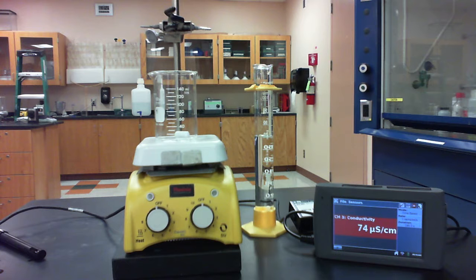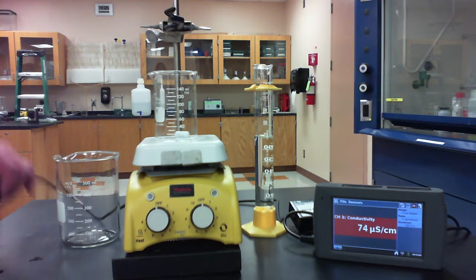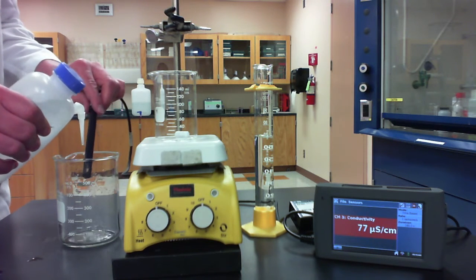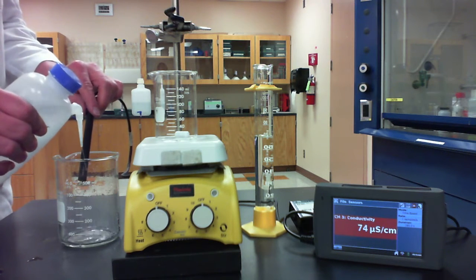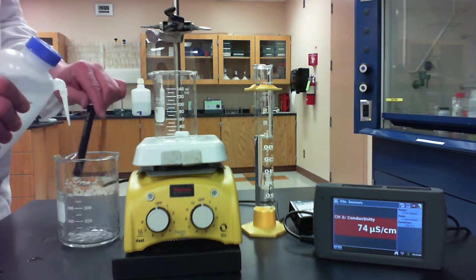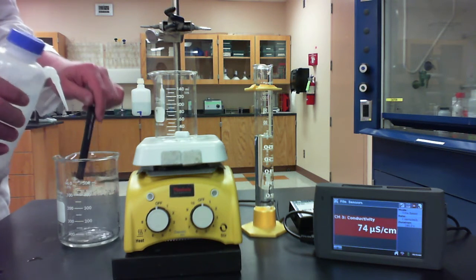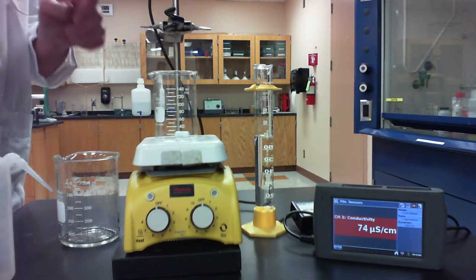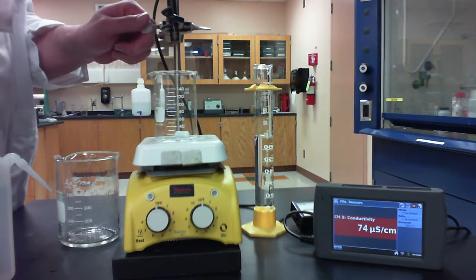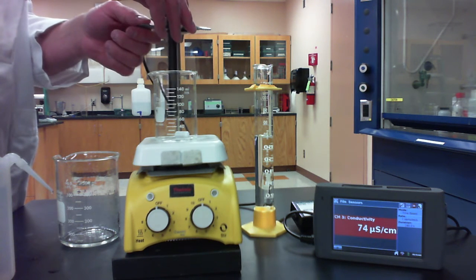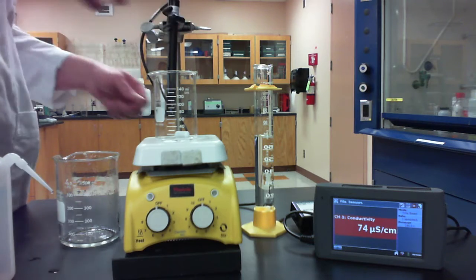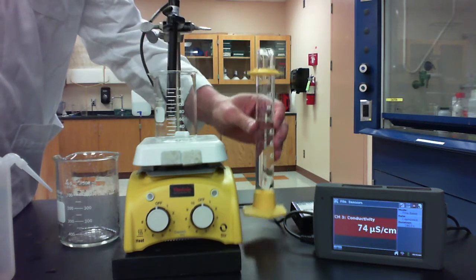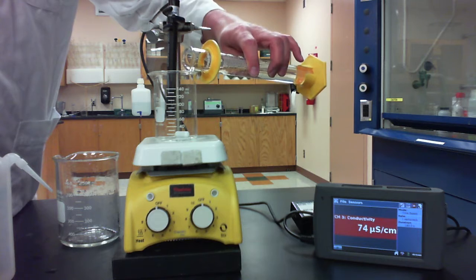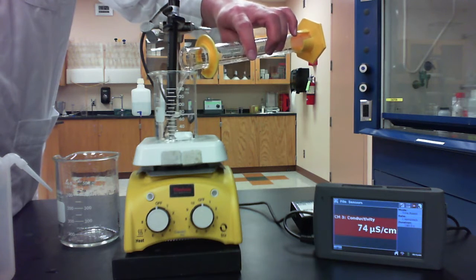Then I will use the wash bottle to rinse off the conductivity probe into a waste beaker. Be sure to thoroughly rinse the probe between each batch of measurements. Then, fix the probe inside of a 3-finger clamp.